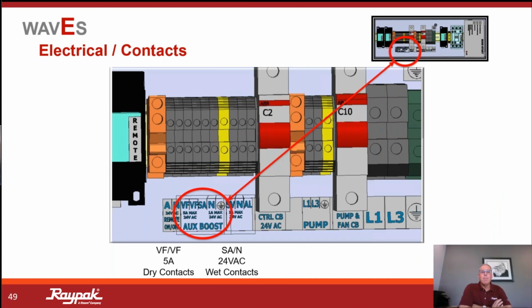Additional contacts: there are a lot of different ways to use these contacts or relays. If you're using a louver proving for air or maybe an additional fan to exhaust, you can use these terminals. One of them is a 24 volt wet contact. It's at the SA and N terminal. And then conversely, these 2 terminals of VF, those are dry contacts that we can switch up to 5 amps through. So again, a little bit of versatility there if you need to switch power or maybe bring on external components, field supplied components. You have some options here when the unit is running.